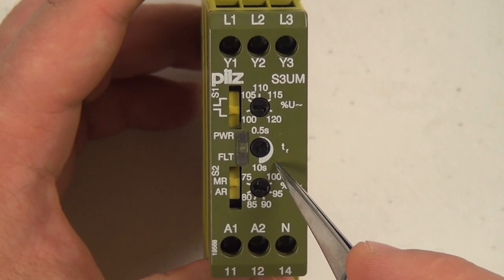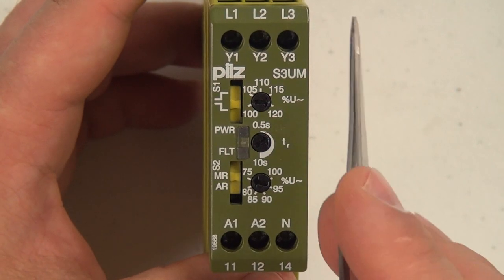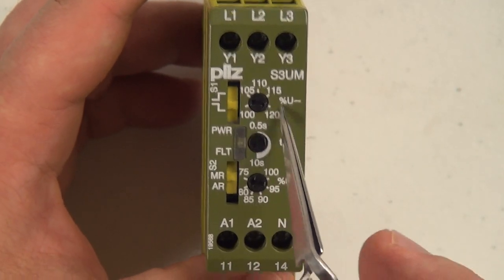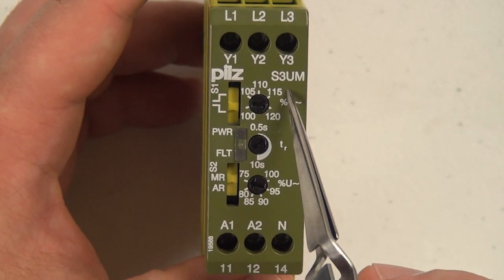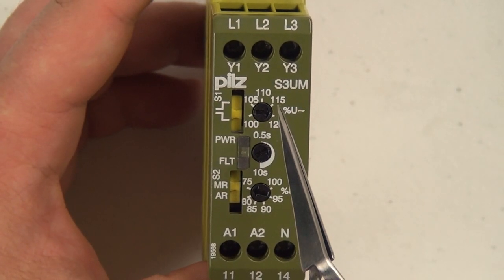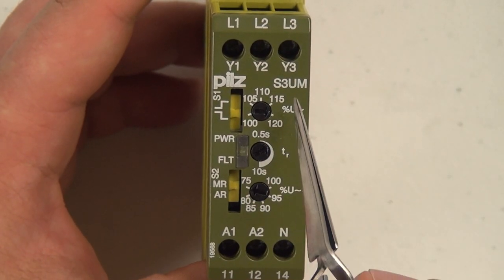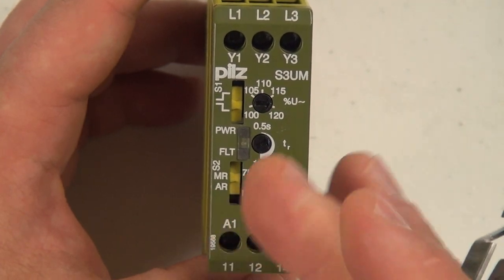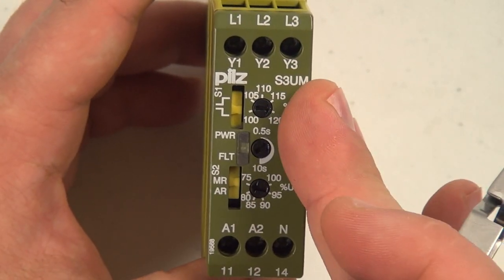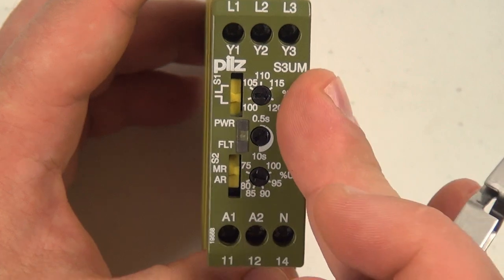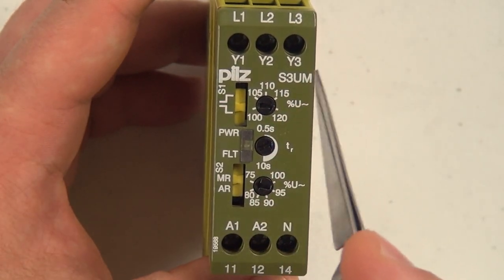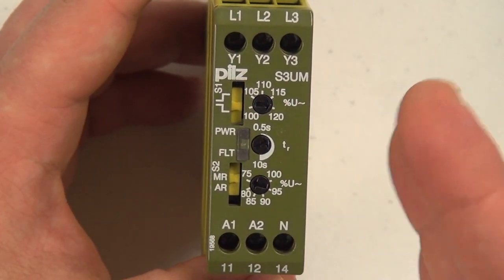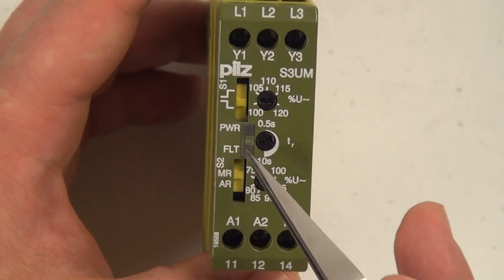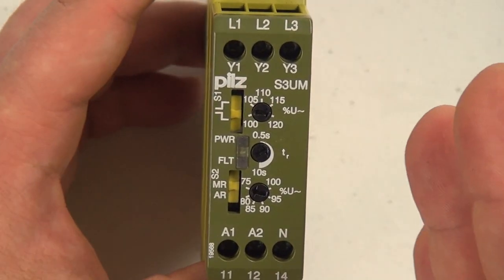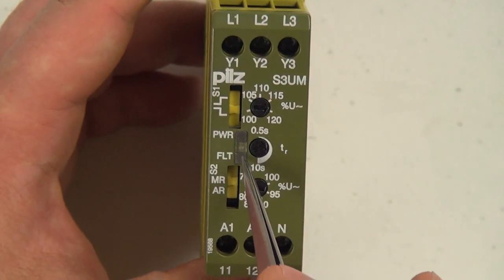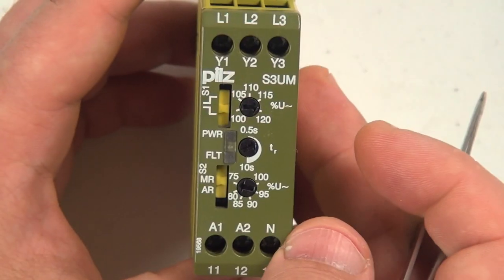I've worked with other power quality relays, like Siemens, for example, makes one that's got a little screen on it. And that little screen gives you a readout of, well, what's my voltage, what's my fault, etc., where just by glancing at the screen, you know exactly why the relay's faulted, and you can go hunt for the problem versus having to figure out what the problem is just from one single stupid light. Otherwise, other than this one light issue, this relay works just fine.